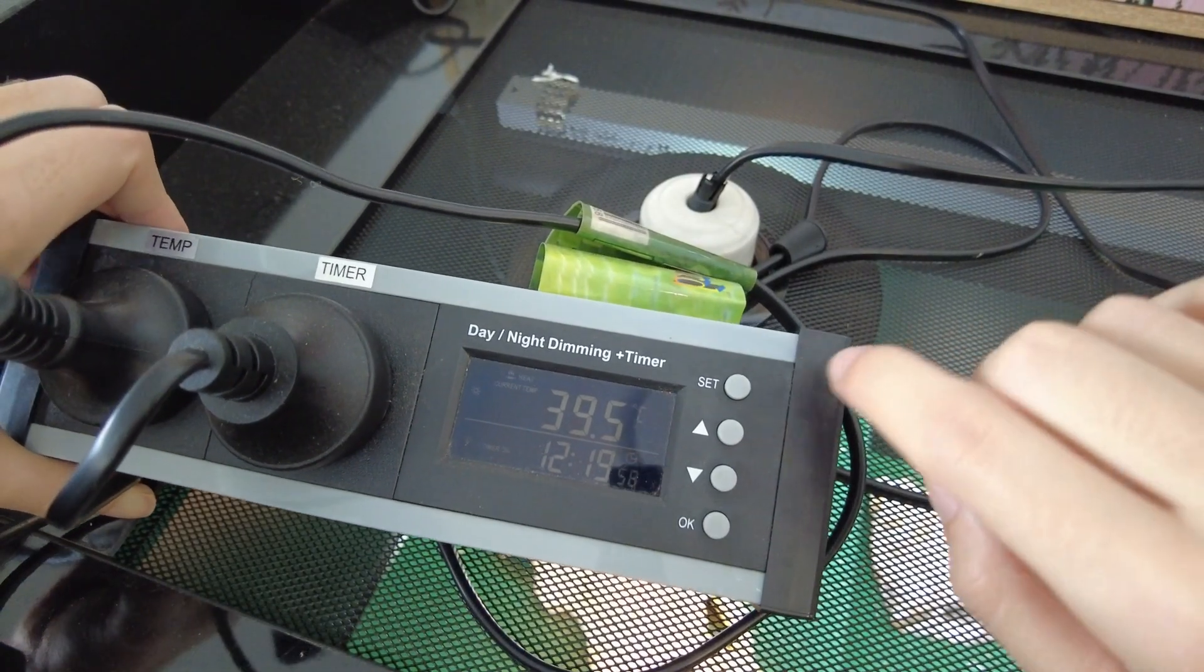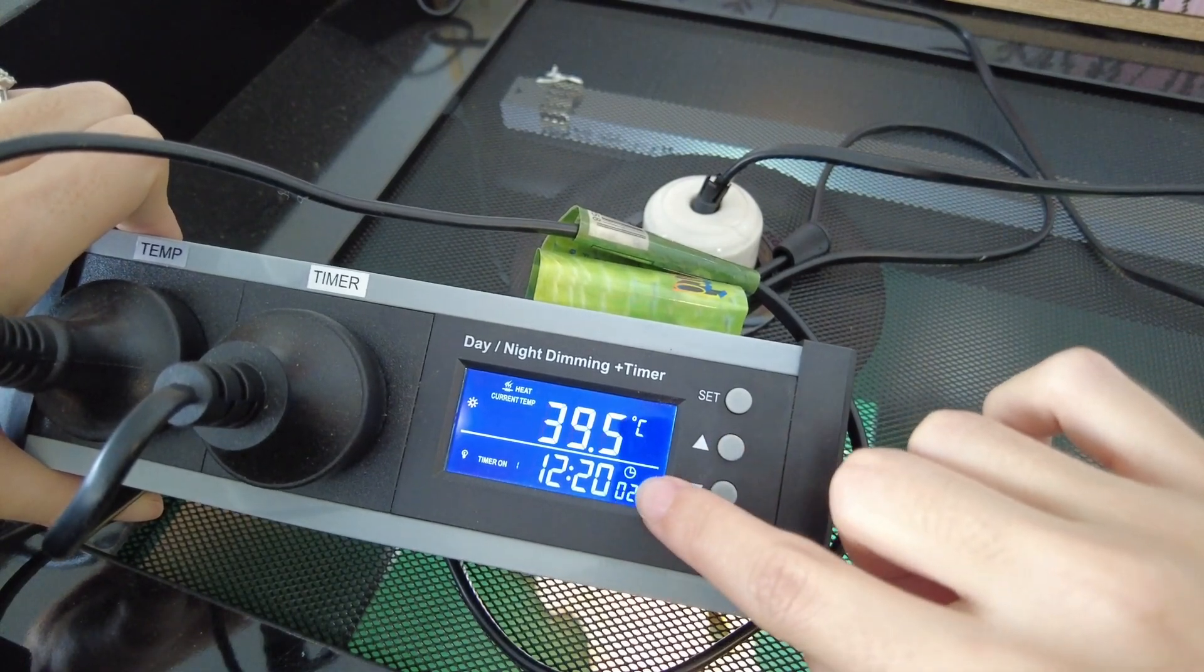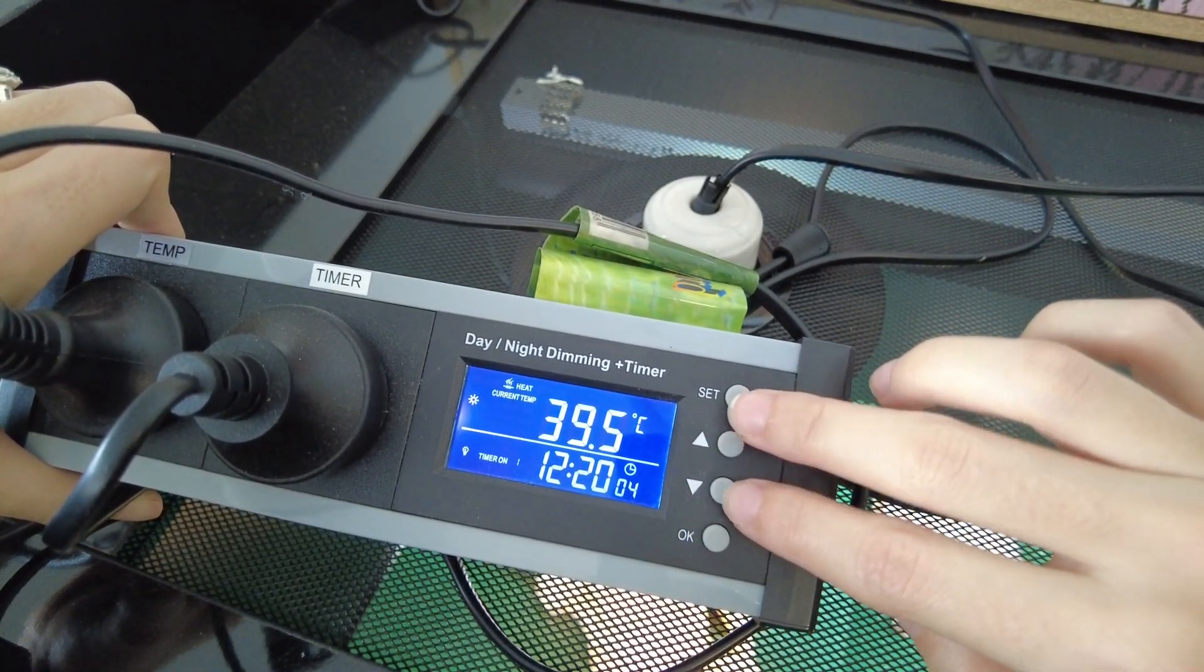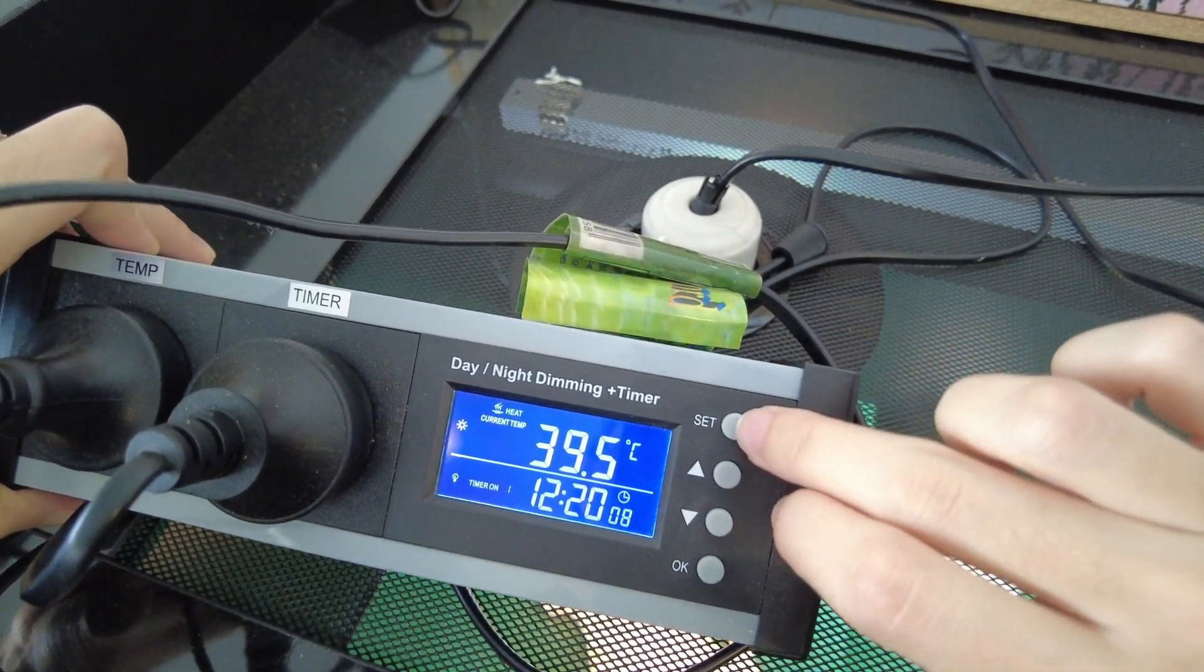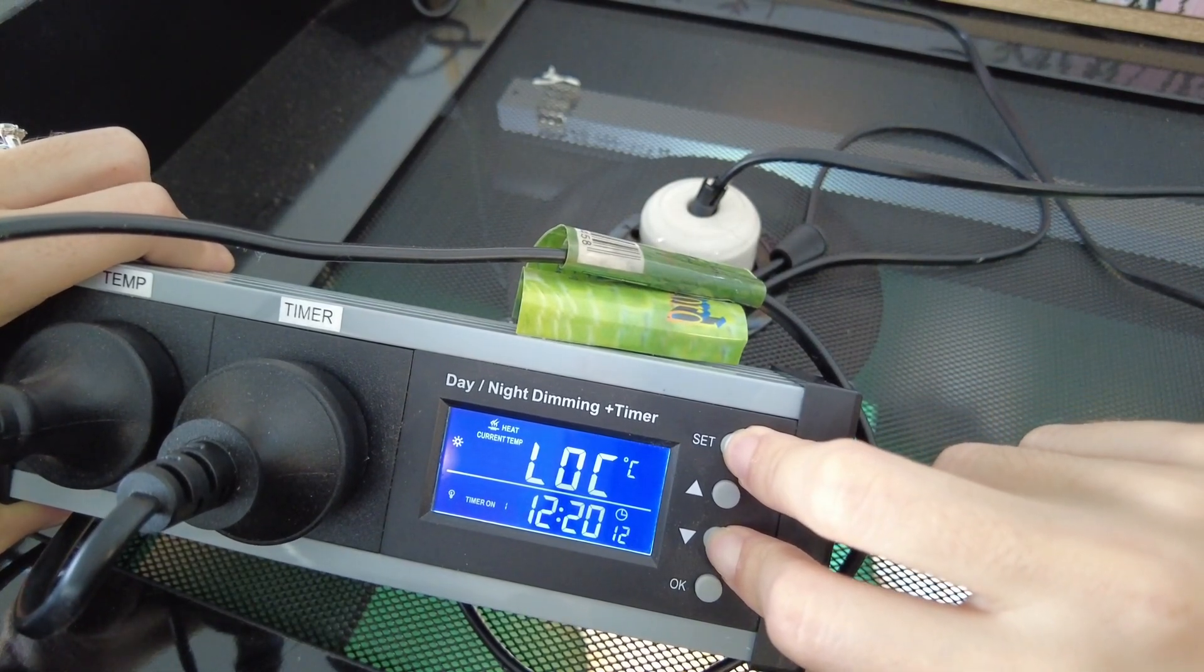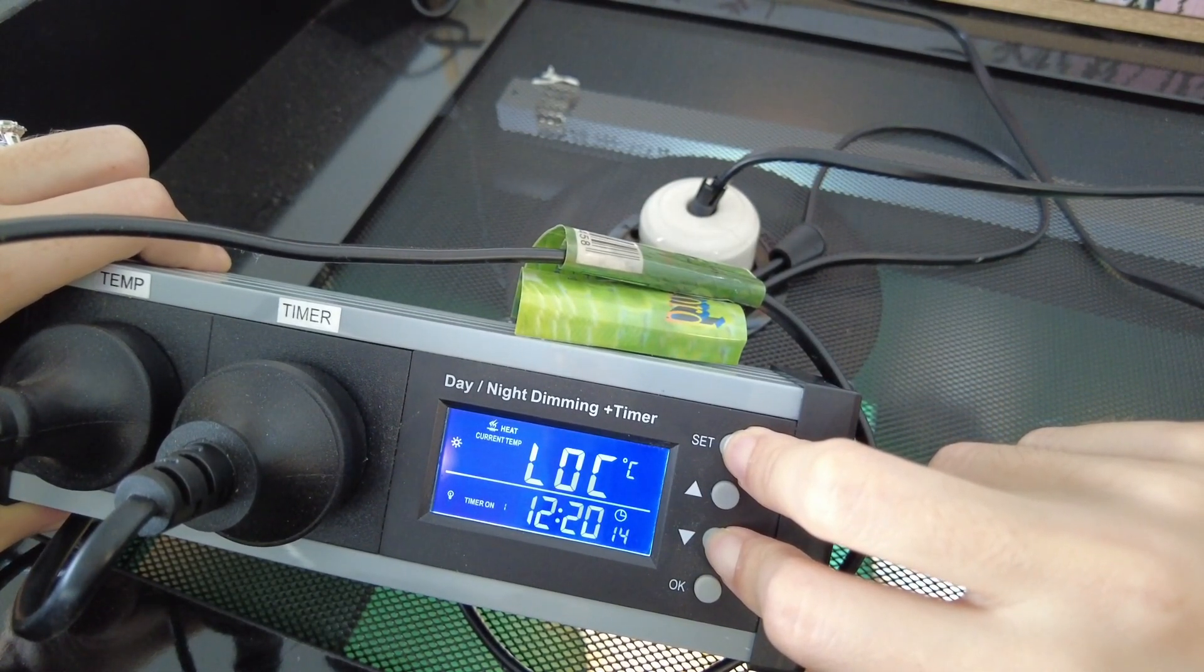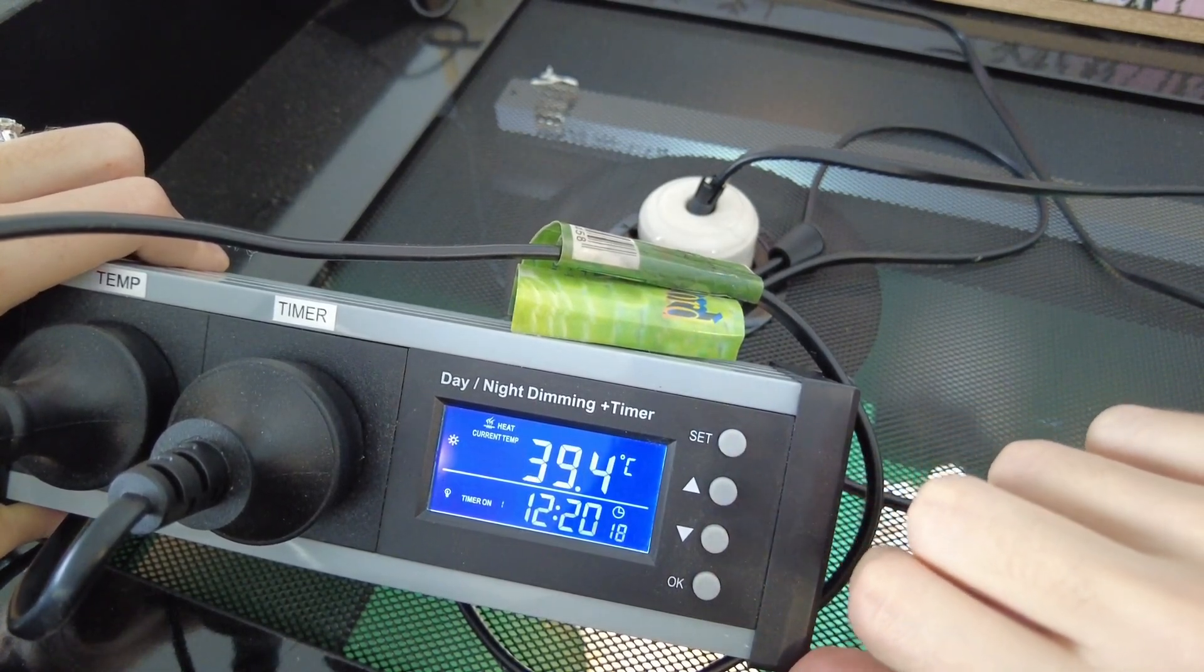Once you've got it all plugged in, if you press any of these buttons it's going to come up with this screen that says lock. So we need to unlock the device first to make changes to it. To do that we need to hold down the set key and the down arrow until that lock screen goes away. Okay, now we're going to be able to make changes.